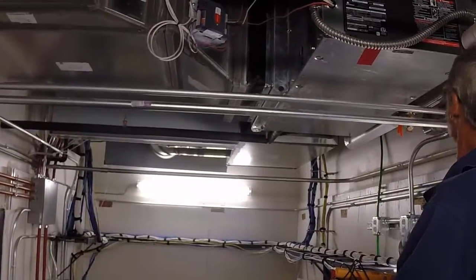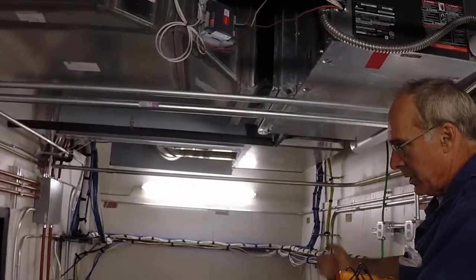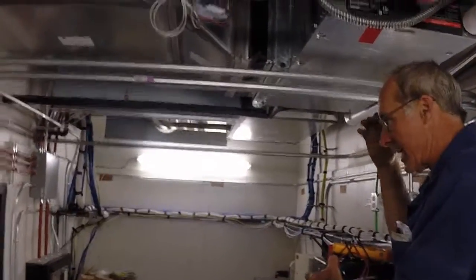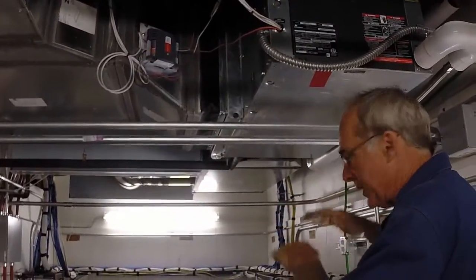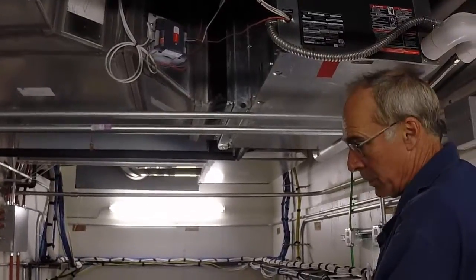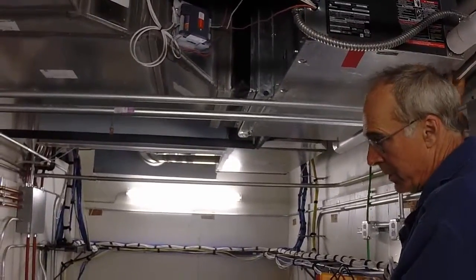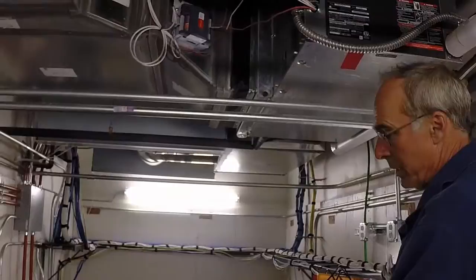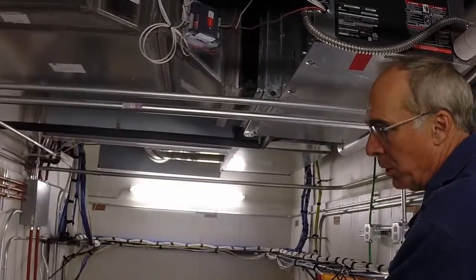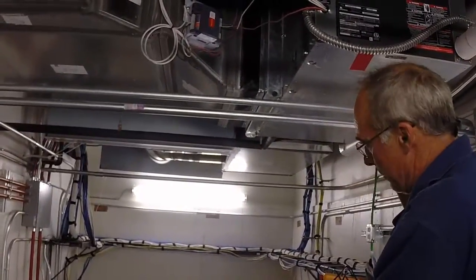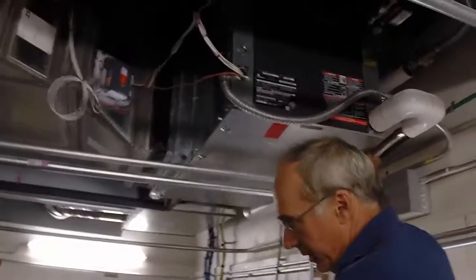On the water side, this goes back to your boiler room, and on this building we have a heat injection system. You have to keep this building loop in a range of temperature. If the water's too cold, I'll start tripping out on alarms. The water's too hot, I'll start tripping out on alarms. You don't ever want to see this water above 100 degrees in cooling season. Heating season would just flat overcook me and overamp me because I'd be trying to cool 100 degree water.